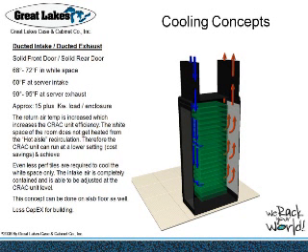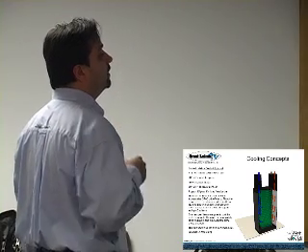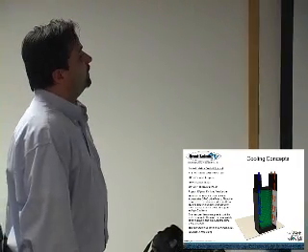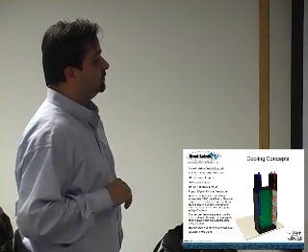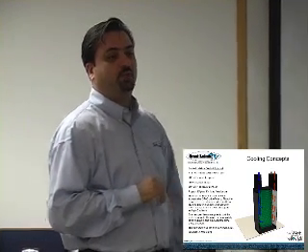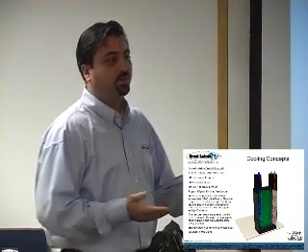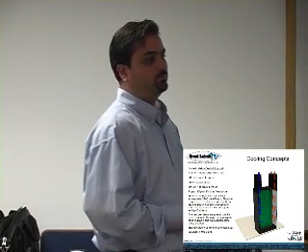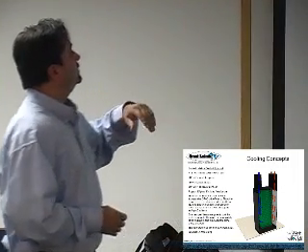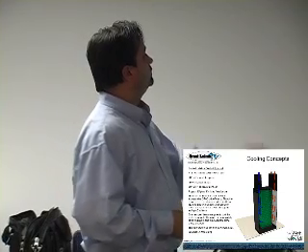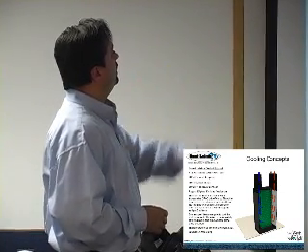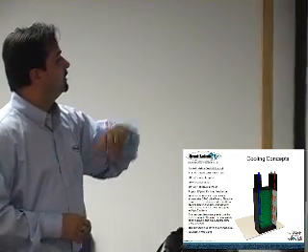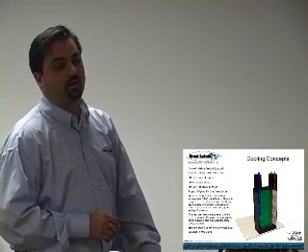Well, and the last one is just following the laws of thermodynamics. Cool air dropping, hot air going out. So, ducted intake, ducted exhaust. And this can be done on a concrete slab floor if needed, and you have no need for a raised floor. But this would be a full build. What happens here is you have a solid front door, solid rear door, 68 to 72 in the white space, basically your own space. Now you can get the exact same temperature coming out of your CRAC.